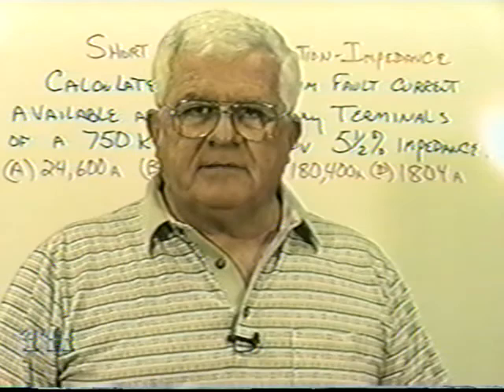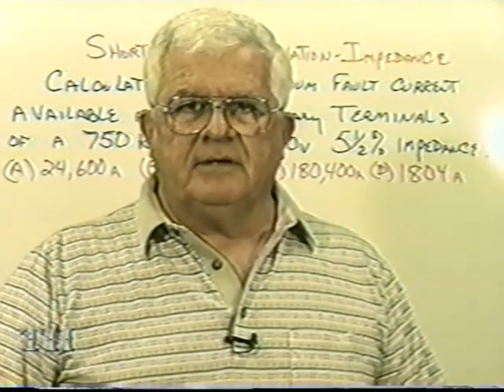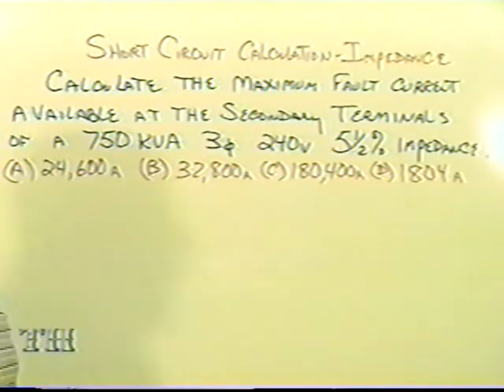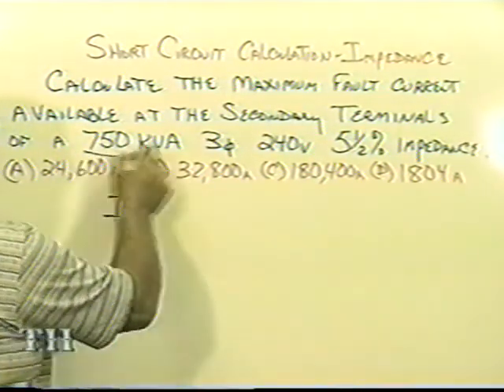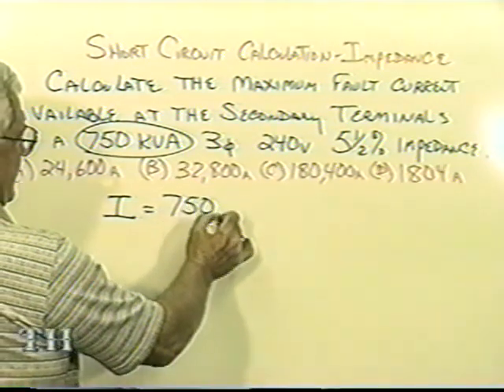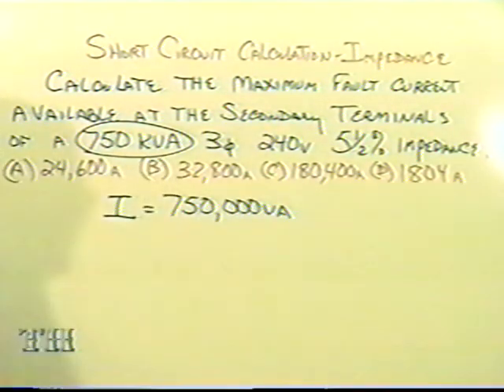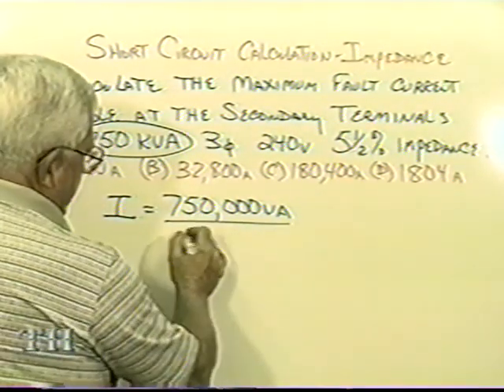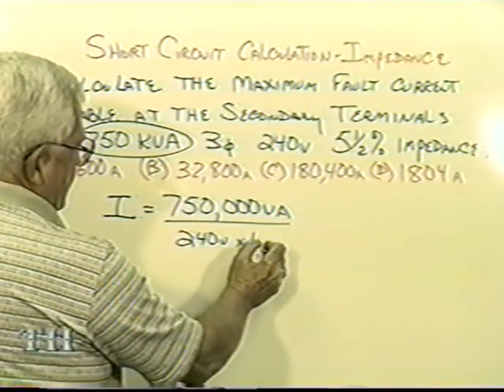Now I have on the board behind me a question on the master's exam from this category that we just discussed. They're saying calculate the maximum fault current available at the secondary terminals of a 750 kVA, 3-phase, 240 volt transformer that has a 5.5% impedance. They give you 4 choices to choose from. Now the first thing I want you to do is find the rated current. Like you would take this 750 as 750,000 VA. See, K meaning kilo. It's at 240 volt at the square root of 3.